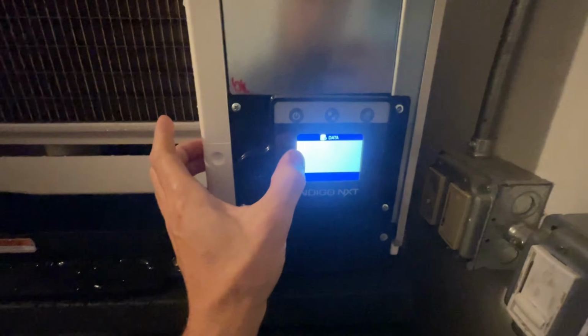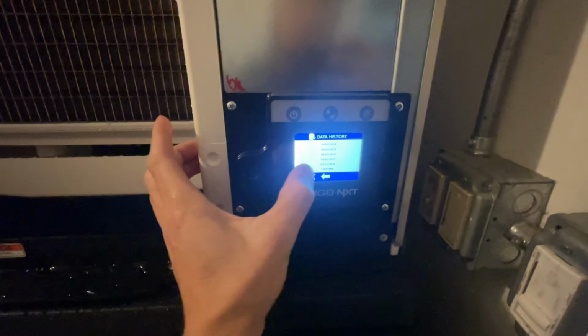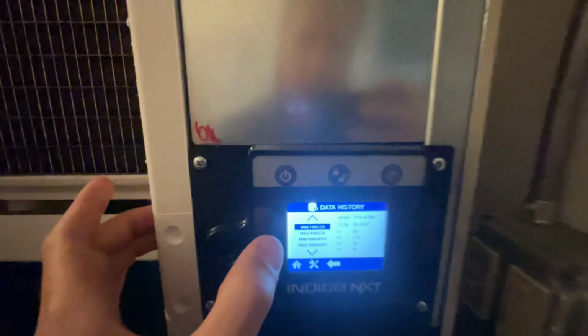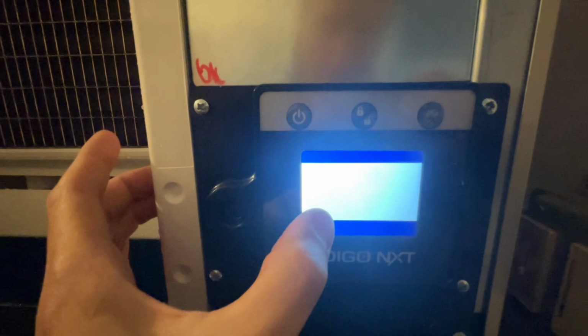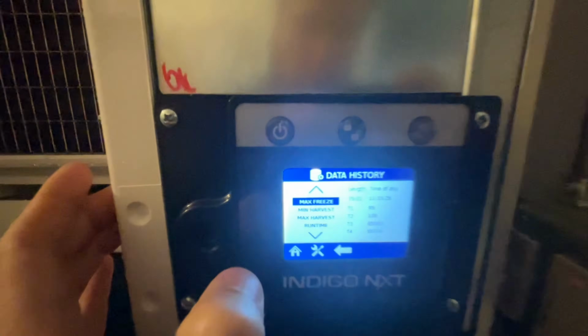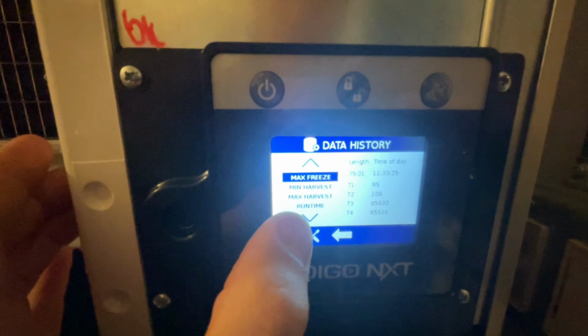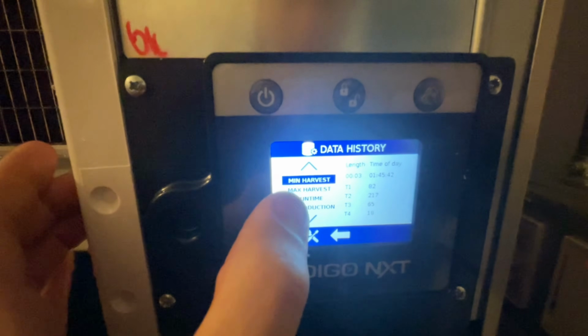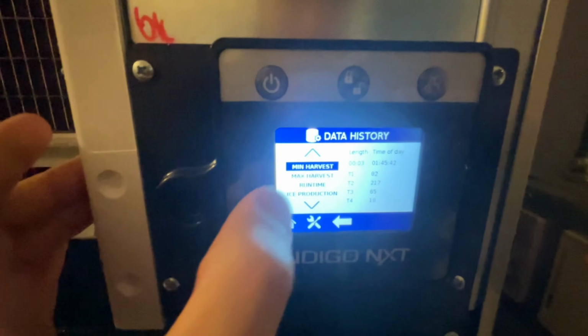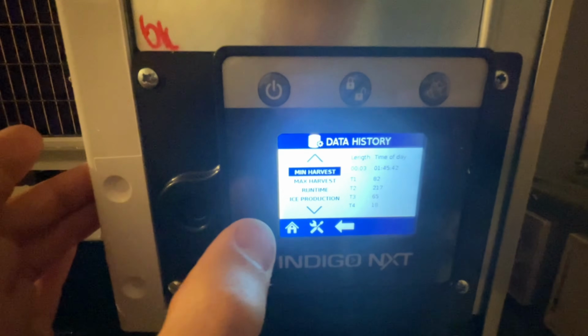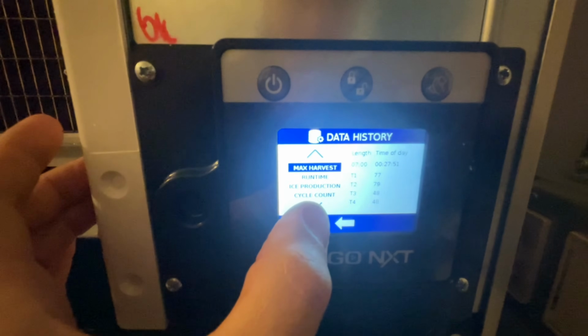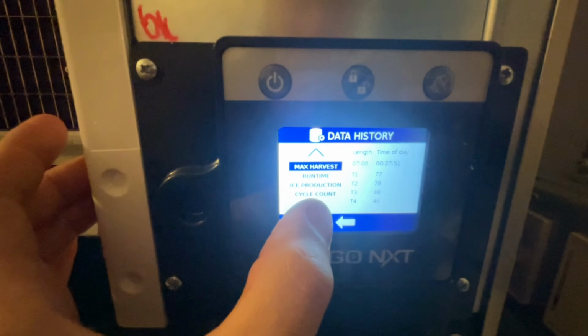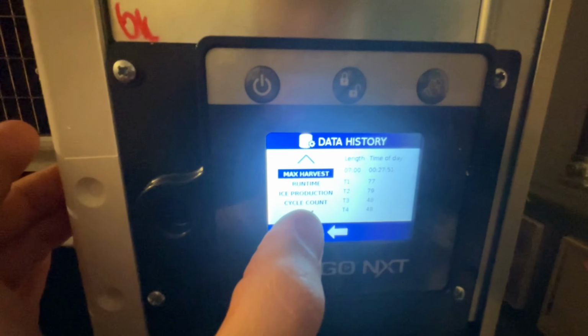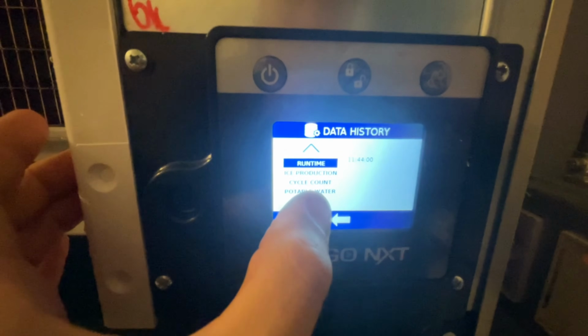A cool thing to check is your data history. It will show you some details: minimum freeze time was 12 minutes, which is normal. Max freeze time was 35 minutes, which is way too long. Minimum harvest time is 3 seconds, which should never be 3 seconds, probably leading us to a curtain fault issue, or excuse me, a bin switch issue, curtain switch. Max harvest was 7 minutes, which should never be 7 minutes.